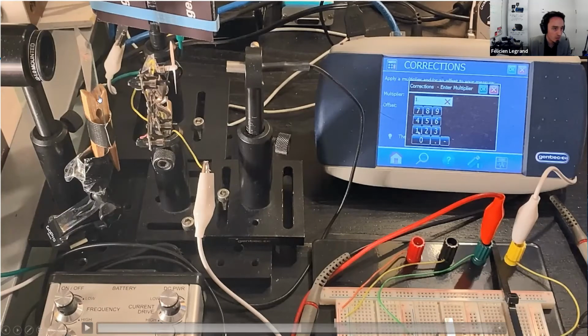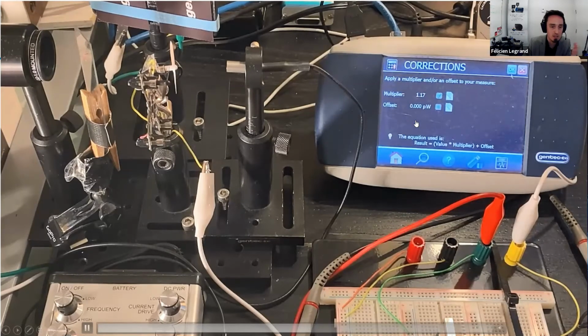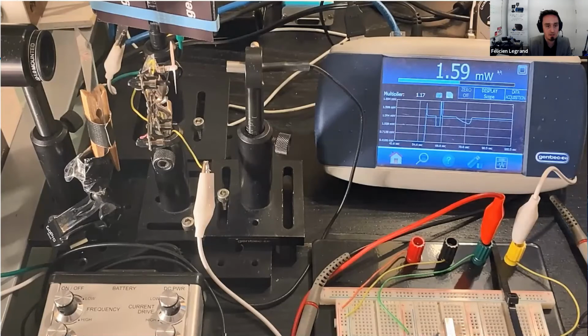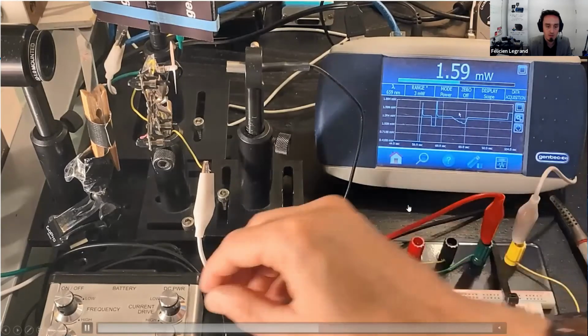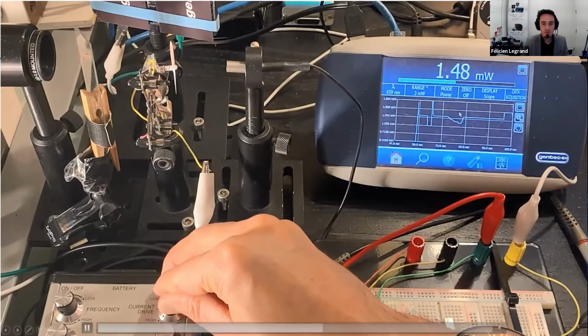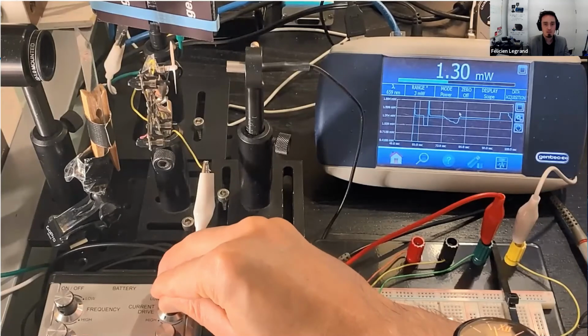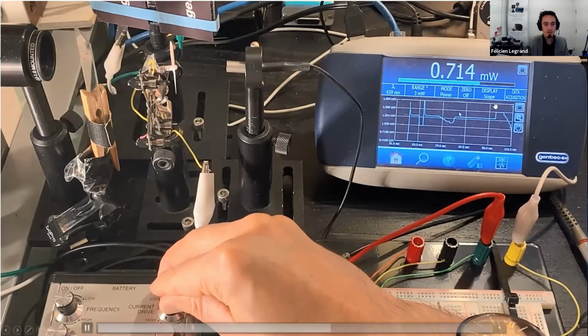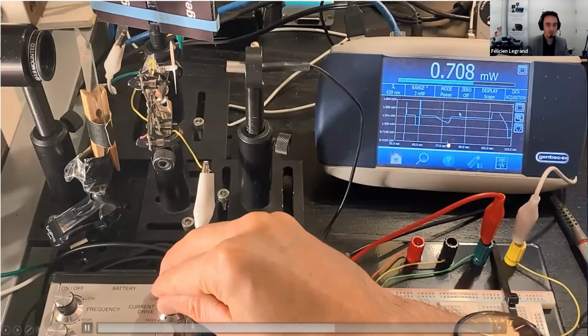And I know the attenuation of this glass piece here; I've measured about 17%. So I need to tell my display that I need to multiply my reading by 1.17 to get back to the actual incoming laser power that the diode is providing. So one thing that's missing is to zero the meter, and I'm going to do that in the next step.